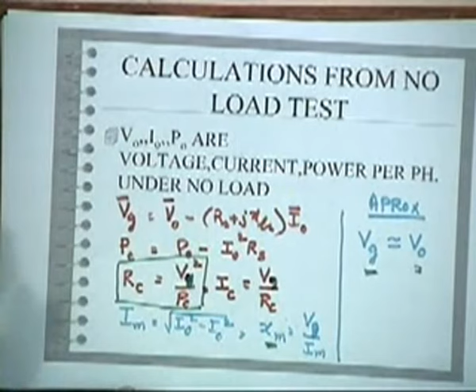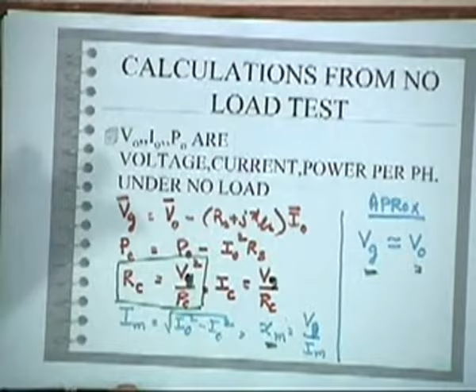So, after determining the currents, voltages, and power on no load per phase, you can calculate the core loss, the magnetizing reactance, the magnetizing current, the core loss current, and the core loss resistance. So all these parameters you are able to quickly determine.